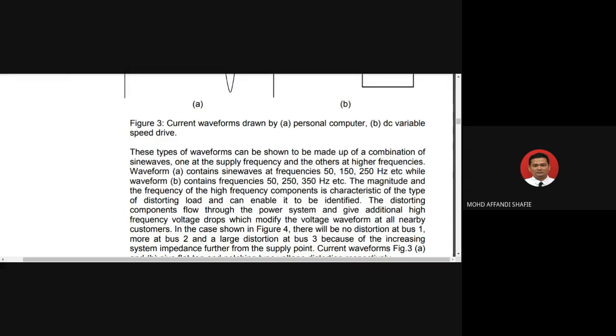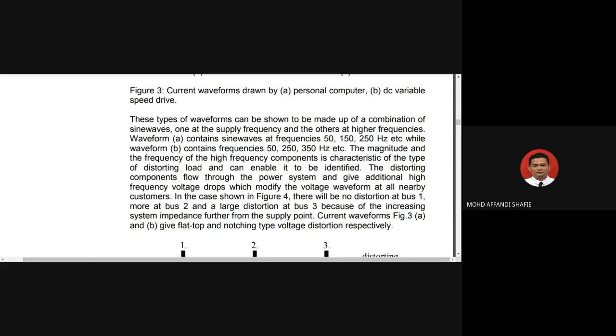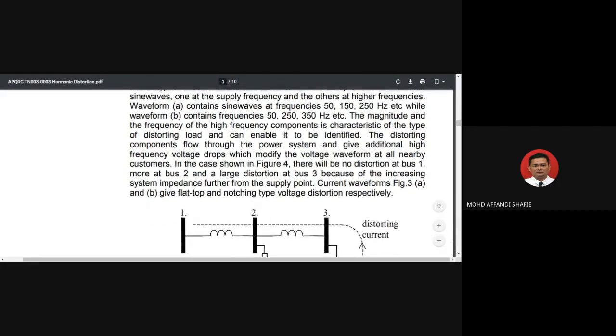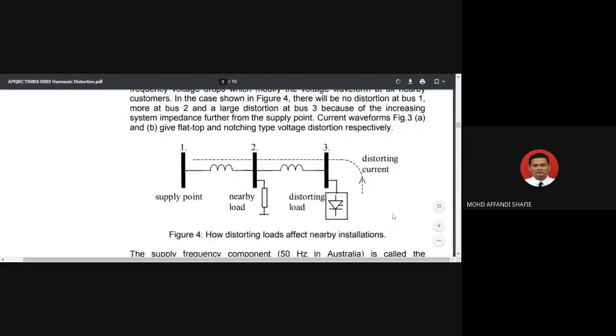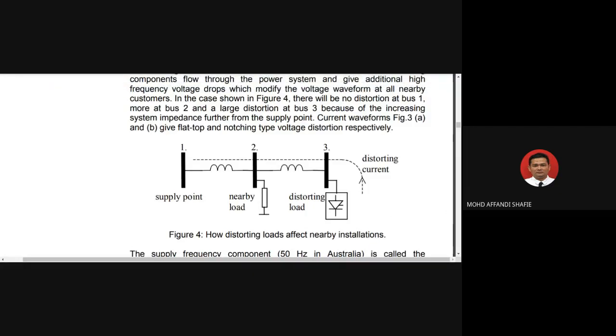So the distorting components flow through the power system and give additional high frequency voltage drops, which modify the voltage waveform at all nearby customers. In the case shown in figure 4, there will be no distortion at bus 1, more at bus 2, and a large distortion at bus 3 because of the increasing system impedance further from the supply point. The current waveforms in figure 3A and B give flat top and notching type voltage distortion respectively.